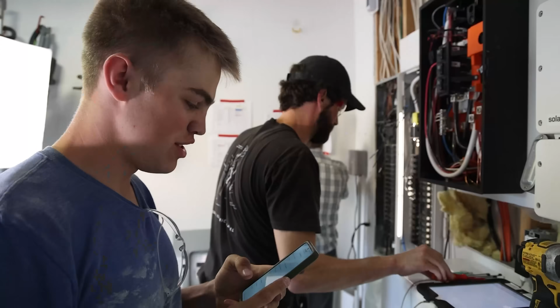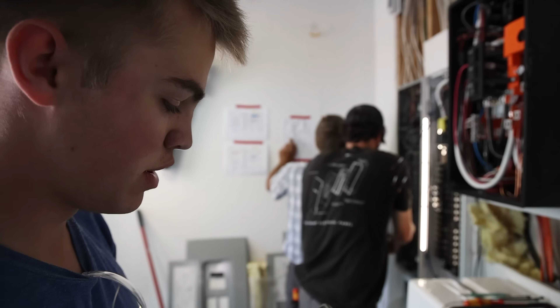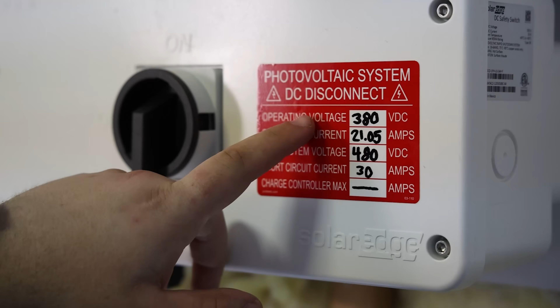Back to work. So now we need to get the optimizers for the solar panels and the inverter all set up to talk to each other. And so you go in the app and you go to pairing, you wait a second as it loads. And this pretty much just takes everything down to 0 volts or like 1 volt. And then it slowly starts recognizing them and adding them to the system, I guess. On here we have our operating voltage, which is standard is at 380. The max voltage we're going to see is 480. The short circuit current is at 30 amps, so everything's going to trip at 30. And then operating current is going to be roughly 21.05 amps.